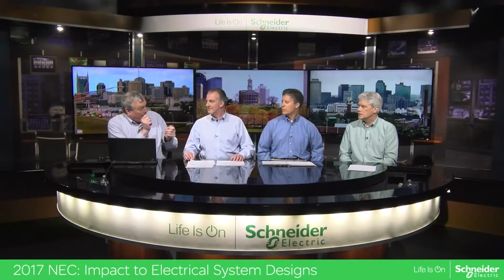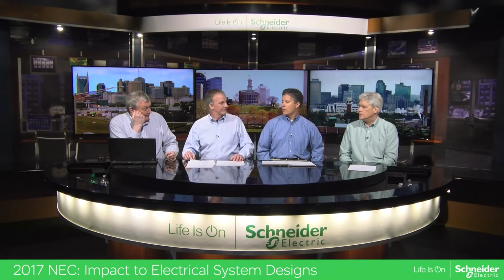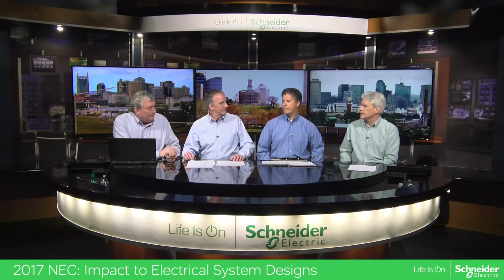Okay. It's interesting, Jim, that you were talking about the commissioning, and Chad, you mentioned the fact that you need to do this primary injection before the contractor hooks it up. How do you balance that? If you're in a commissioning mode, you've got all the connections made. You're going to ask them to unconnect and hook up the primary testing? It's going to have to be part of that test plan, and you're going to want to look at what load is available to get the system operational and performance verification. And then if you're going to come back in and do the testing, it means disconnecting stuff. So nobody's going to like doing that. It's one of the largest challenges with this.